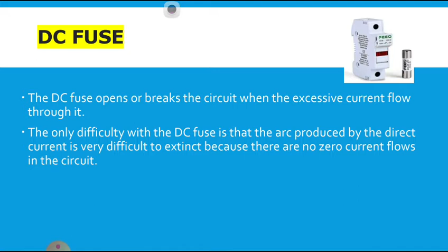For reducing the DC fuse arcing, the electrodes are placed more distance apart, due to which the size of the fuse increases as compared to the AC. So it is of bulk size. What will happen if the two contacts are close to each other? There is a possibility that ionization takes place once again in the air between the male and female contacts, and there is a possibility of arcing again. To avoid that, we increase the separation distance, thereby the size of the fuse also increases as compared to AC fuses. Now this is one thing.